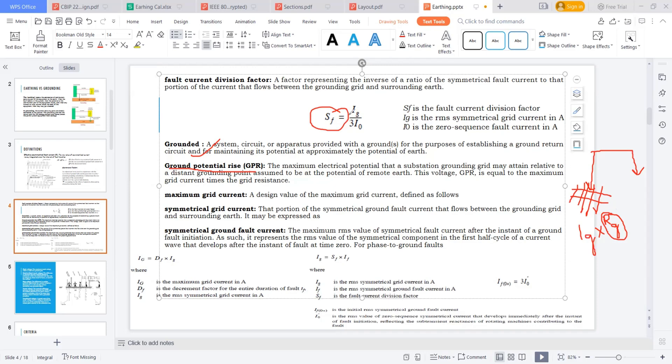How can I know this IG? I get IG from 3I₀ times SF. I know 3I₀: 25kA for 33kV, 40kA for 220kV. So I get IG. If I multiply IG times RG, the product is a voltage that will develop. That voltage is ground potential rise.